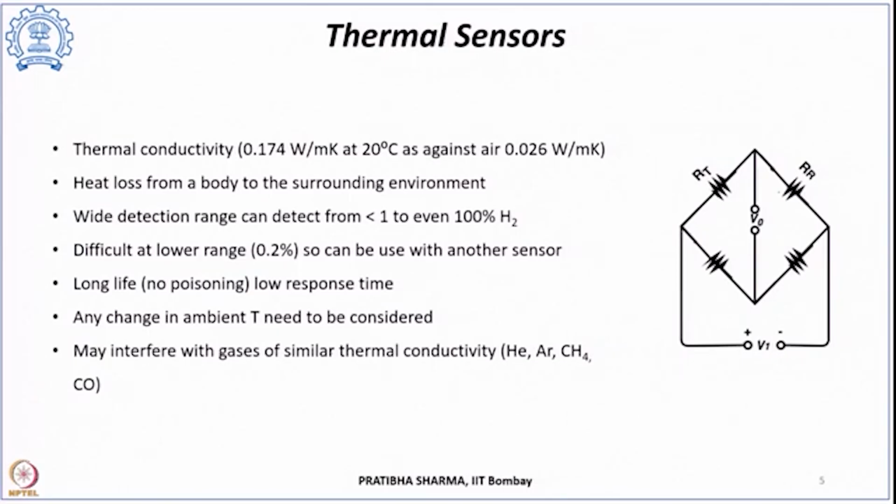These type of sensors do not get poisoned by the hydrogen or the presence of other gases. So as such there is no poisoning effect and the life of these sensors is long. It is more than 5 years of operation. They have a very low response time, reported like 5 seconds even.